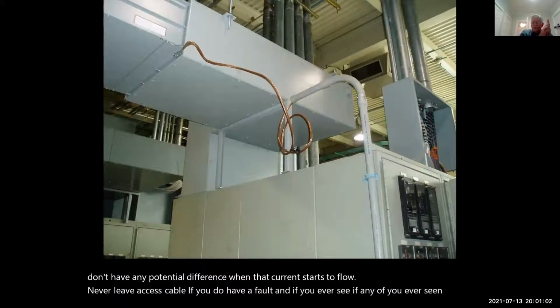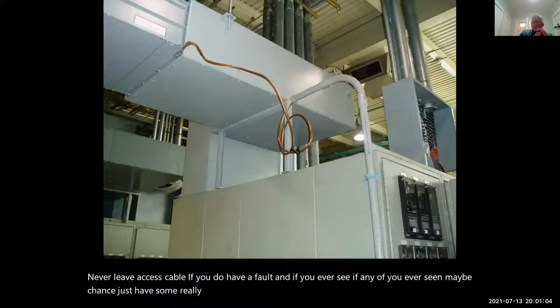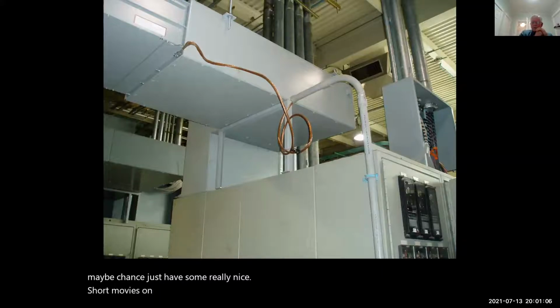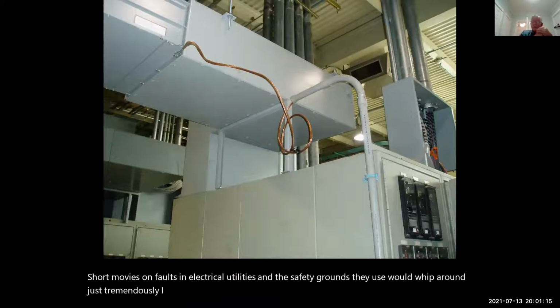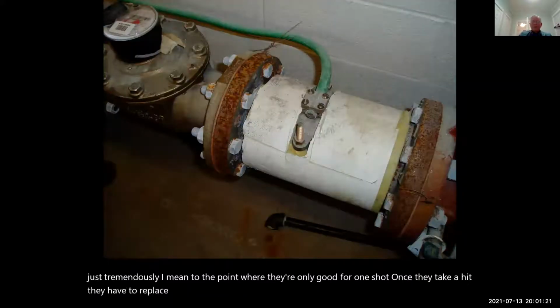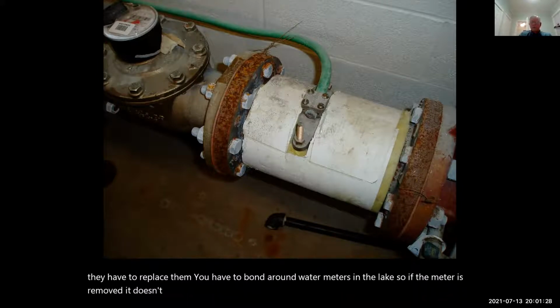Chance used to have some really nice short movies on faults in electrical utilities, and the safety grounds they use would whip around just tremendously. I mean, to the point where they're only good for one shot. Once they take a hit, they have to replace them. You have to bond around water meters and the like. So if the meter is removed, it doesn't create a discontinuity.